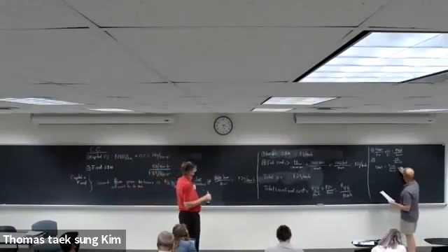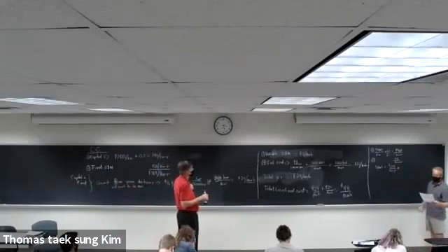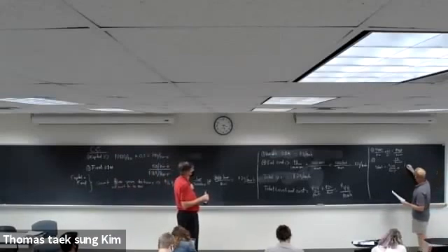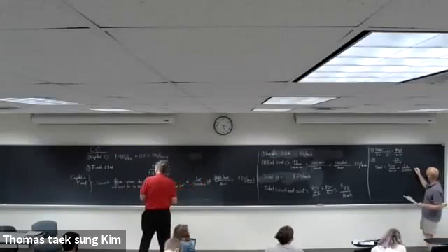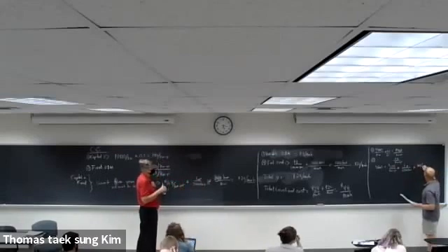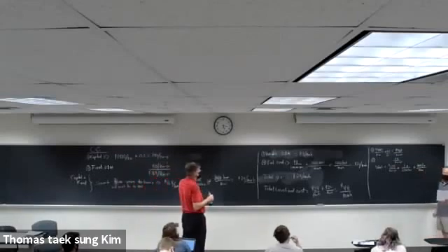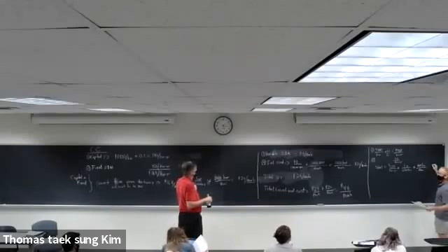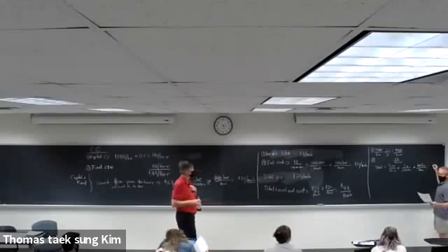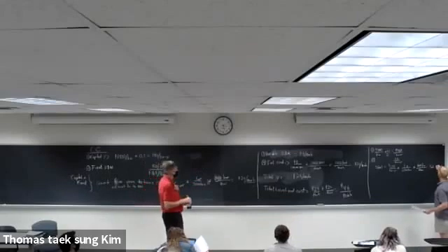So we multiply this $105 per kilowatt-year by 1 year divided by 2,000 hours, and then we do our 1,000 kilowatts per megawatt conversion. 105 divided by 2,000, multiplied by 1,000, is 52.5. Awesome. See, I had that already done.